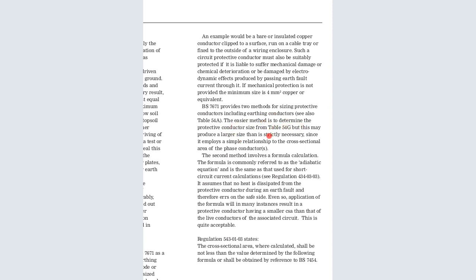The easier method is to determine the protective conductor size from the table, that is Table 54G, but this may produce a larger size than is strictly necessary, since it employs a simple relationship to the cross-sectional area of the phase conductors. The second method involves a formula calculation. This formula is commonly referred to as the adiabatic equation, and it is the same as that used in short circuit current calculations. It assumes that no heat is dissipated from the protective conductor during the earth fault, therefore it errs on the safe side. Even so, application of the formula will in many instances result in a protective conductor having a smaller cross-sectional area than that of the live conductor.